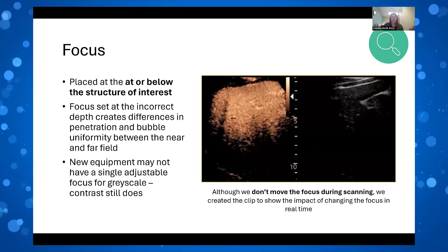It is worth a note that new equipment has moved away sometimes from having a single focal zone and is focused across the entire image for grayscale ultrasound. In general, what we've noticed is that the contrast settings still do have a focus that you can set independently. So we suggest that you just double check your equipment before you start your exam.